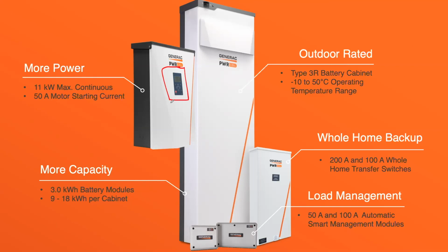It's really easy to program any one of those presets on your system so it'll operate on that schedule. Anytime you want to override it, just walk up to the screen and change the system mode to the one you want for that time. The schedule will pick back up at its next scheduled change, and if you want to disable it, that's also easy to do from the display.